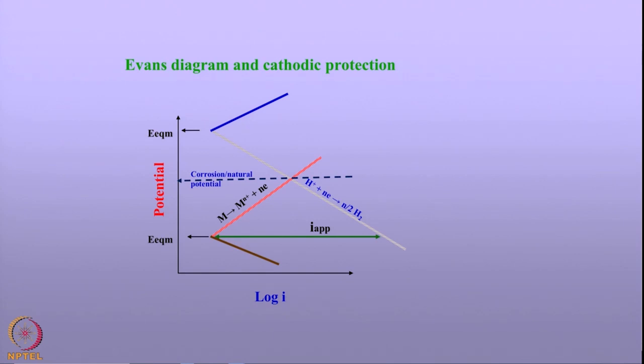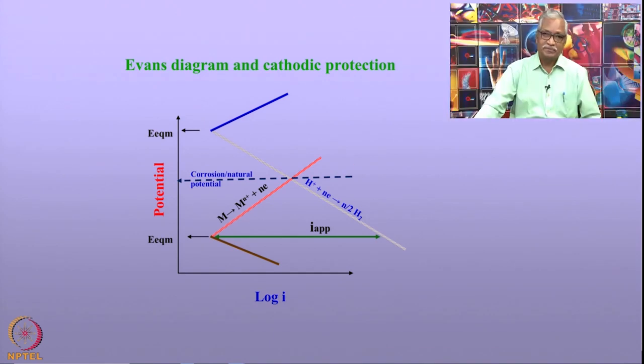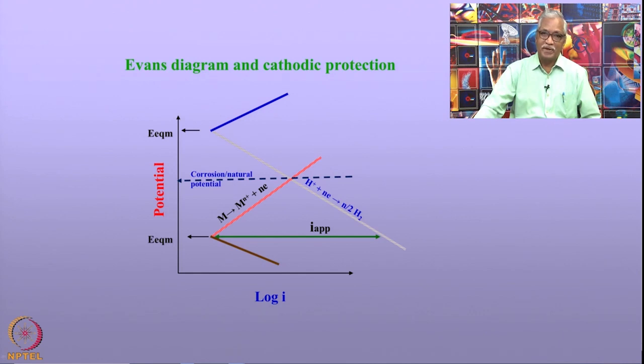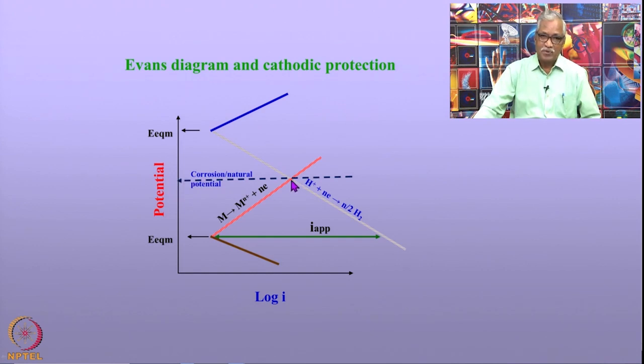We have seen this in the last couple of lectures. The cathodic protection criteria will be discussed in relation to this diagram. When you have a structure buried in an electrolyte or in the soil, it exhibits a potential called the natural potential or corrosion potential. Corresponding to this potential, the metal dissolves at a rate given by the corrosion current density.